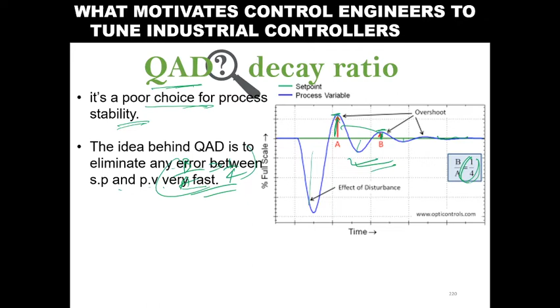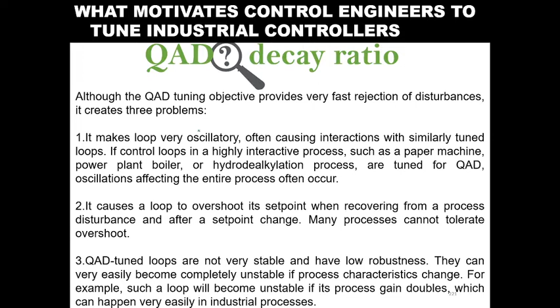So the ratio of B to A is 1 by 4, and this is the quarter amplitude decay ratio. However, it is a poor choice for process stability. The idea behind the QAD is to eliminate any error between set point and process value very fast, meaning it should settle as quickly as possible. So this is the idea that with 1 by 4, it dies out quickly, nothing else. Although the QAD tuning objective provides very fast rejection of disturbance, it creates 3 problems. However, leave this, it is not for your interest.